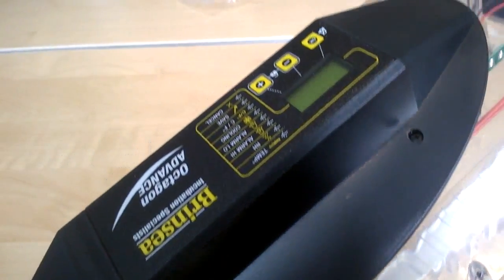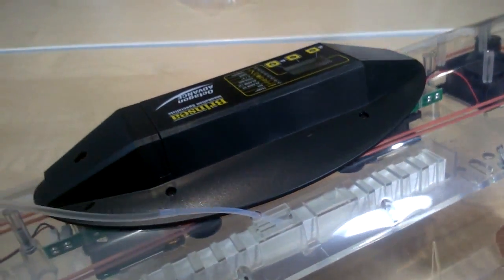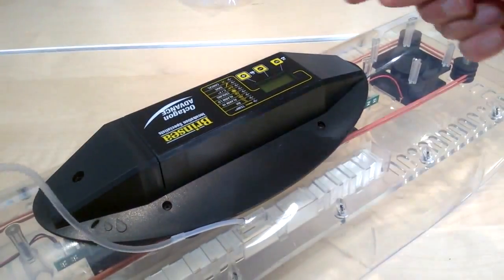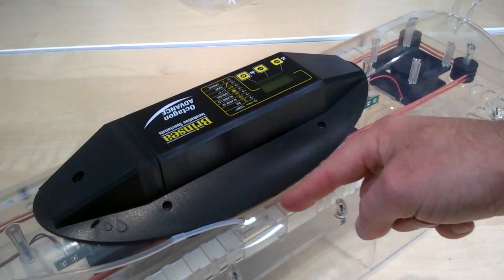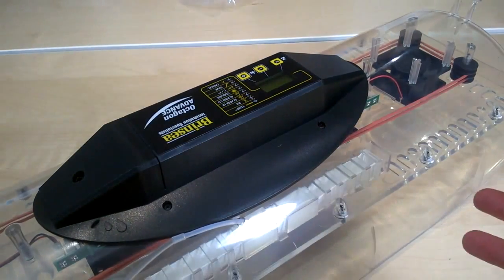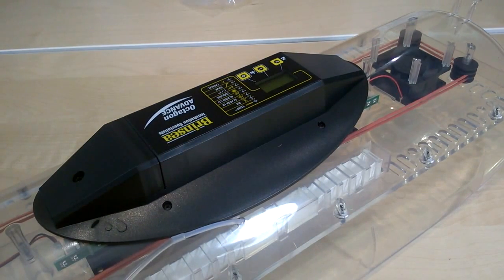So as the pump is feeding water through this silicone tube, it is dripping into the evaporating card, making that moist. And it's as simple as that to set up the evaporating card in the Octagon 40, along with this piece of rigid tubing, which then connects to your pump. Otherwise, it's no different to the Octagon 20.